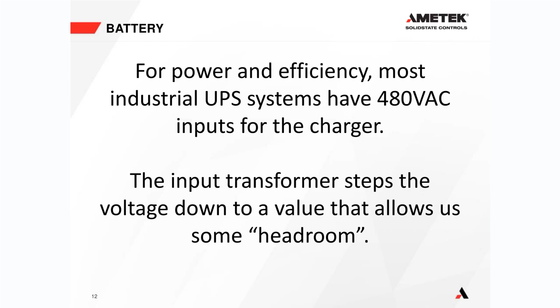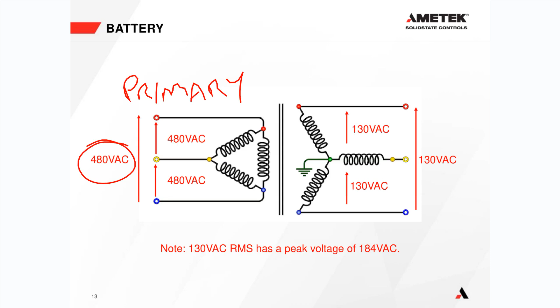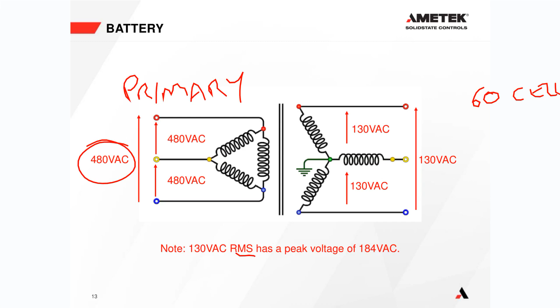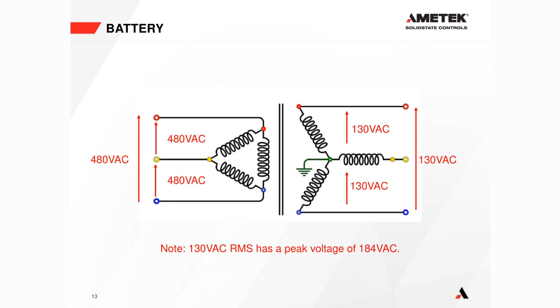So basically, you can see here on the left-hand side we've got the primary, excuse my handwriting, and that's our 480 volts phase-to-phase input. And for a 60 cell lead acid battery, we are going to have roughly 130 volts phase to phase. Now note that 130 volts RMS, which is what you measure with a Fluke 87 meter or anything else, actually has a peak, not a peak to peak, a peak voltage of 184 volts AC.